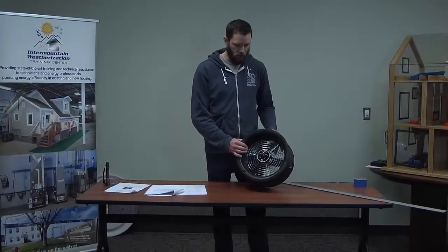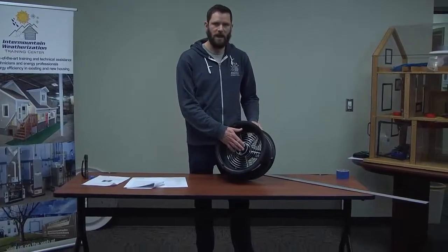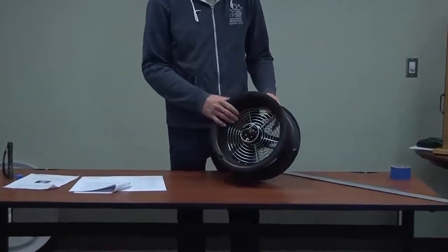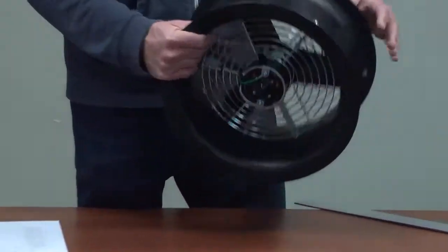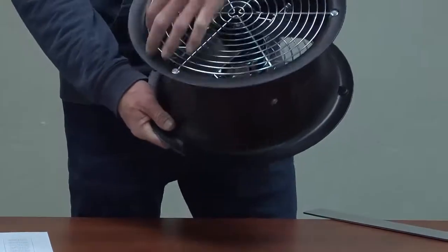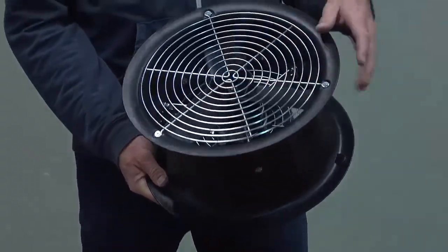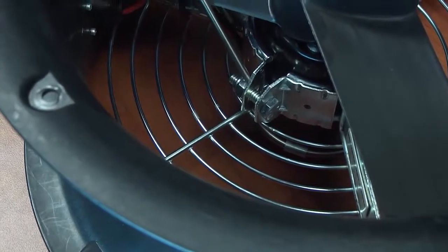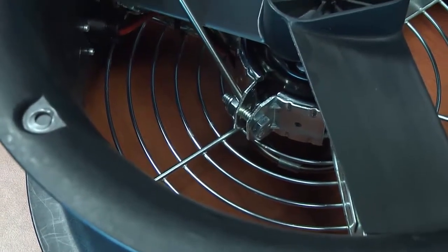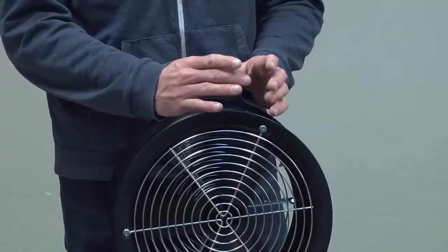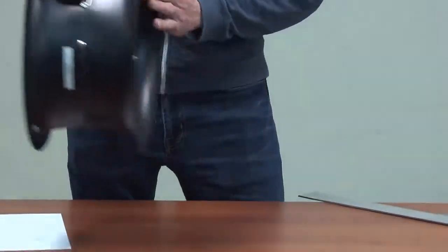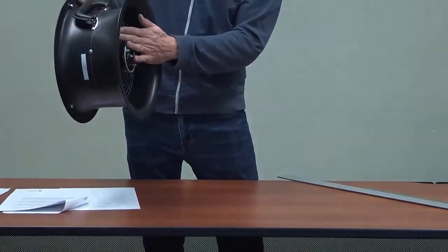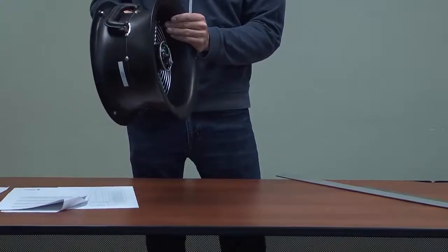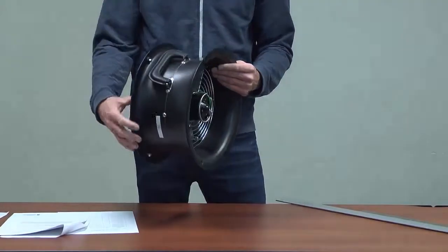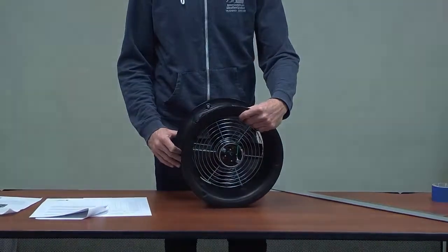All right, so if it was out of those ranges, same thing as on the blower door, you take off this cage housing on the back side, and there's a motor mount inside of there that you can loosen up and adjust and pull that flow sensor either out or push it back in just a little bit to make the adjustment so you're within the specifications of 5/8 to 7/8.